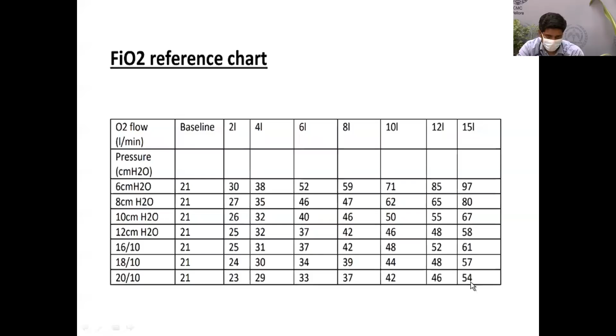And as you can see in the BiPAP as well, at 2 liters, when you have an IPAP of 20 and an EPAP of 10, you can see the FiO2 delivered is 23, and at 15 liters, the FiO2 drops down to 54. So as you go up on your pressures, the FiO2 decreases and oxygen gets wasted.